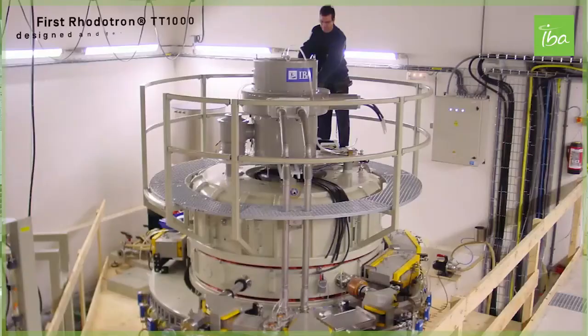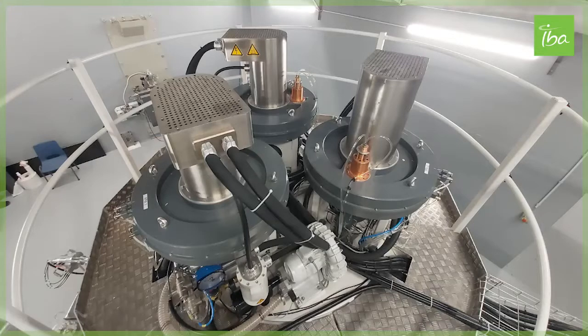Michel, I would like to go back a little bit. The first TT1000 was introduced in 2000, I think. And as we have shown in the previous webinar, the main difference between an EB machine and an X-ray machine is the efficiency of the conversion, which is typically 10 to 12%, so this machine needs to make very high powers. To have 60 kilowatts of EB, you need 600 kilowatts of X-ray. So the source of power is really the main difference between an EB machine and an X-ray machine, right? Yes, that's why we have to equip the machine with three RF systems. That gives us a total power of a bit more than 800 kilowatts. 100 is used for the cavity, the rest is for the beam.